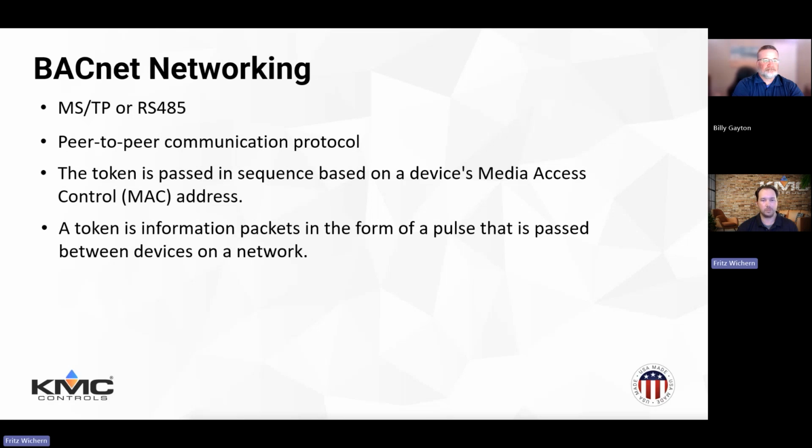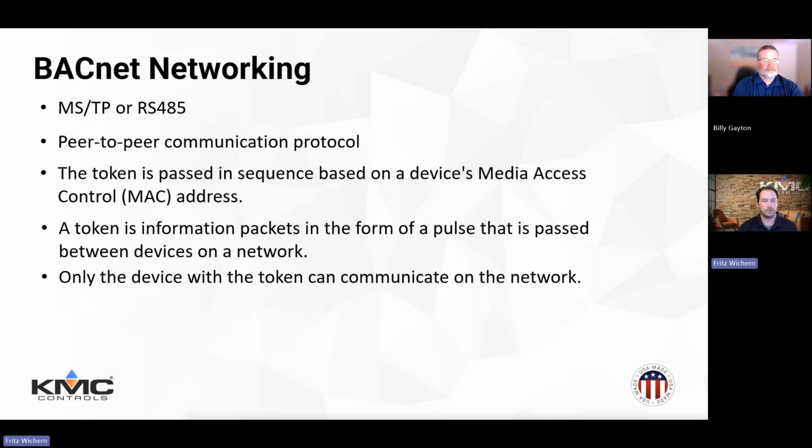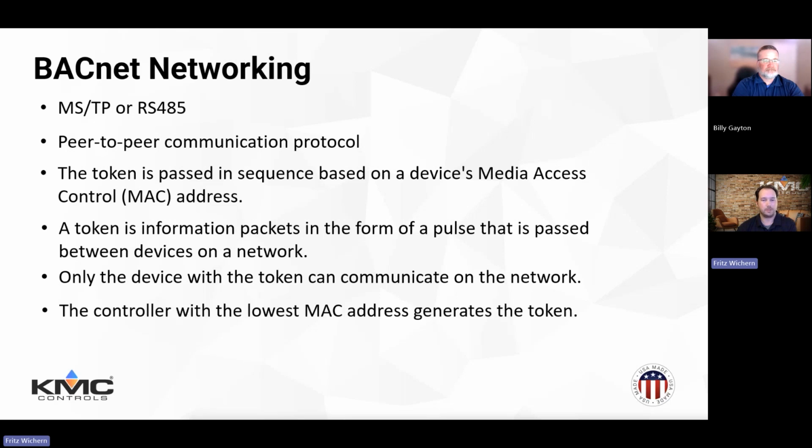Some key points here: only the device with that token can communicate. So it's like a group of people standing in a line. If they all try to talk to one another, communication is not going to be great. But if you give one person a microphone and they are the only person who can talk, right, communication gets a lot better. There are rules that dictate how long the device can have the token and how much information it can transmit. And then the controller with the lowest MAC address generates the token.